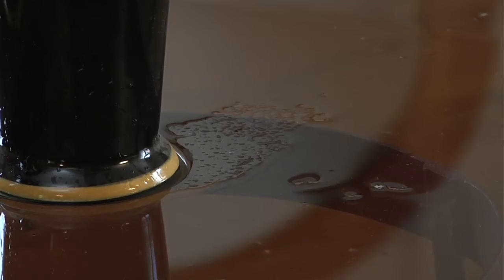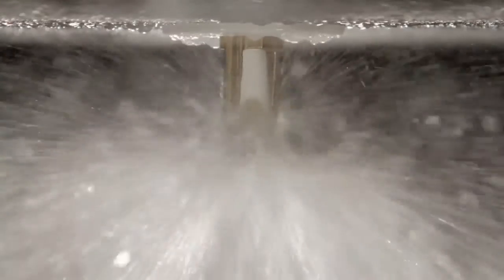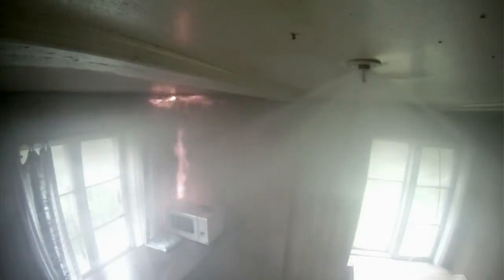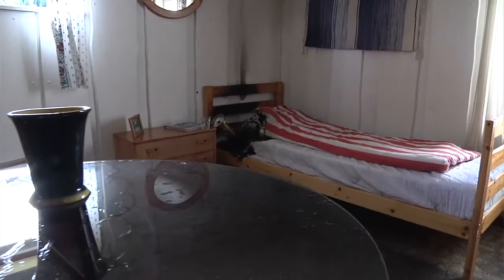Water mist generally contains a lot less water than a sprinkler system. A sprinkler is going to be discharging approximately 85 to 90 litres a minute, and the damage can actually ruin the structure of a building through corrosion. With a water mist, it's a really fine system — you could literally walk through it and come out feeling mildly damp, not soaking wet. Afterwards, there's a lot less clean-up and a lot less disruption to the client.